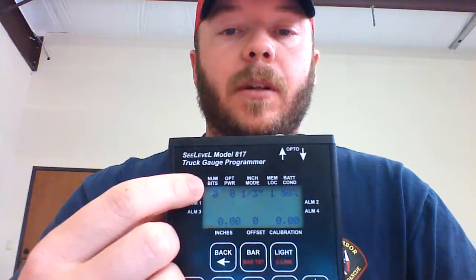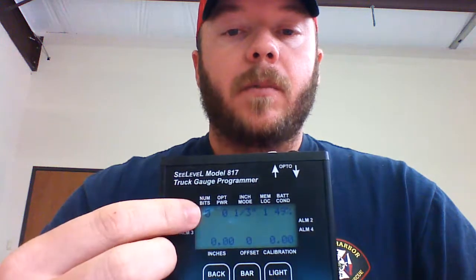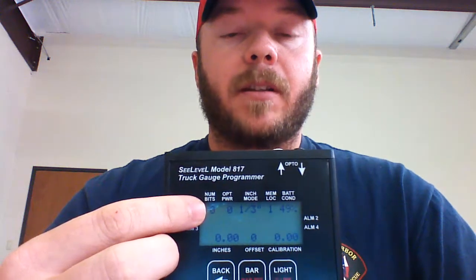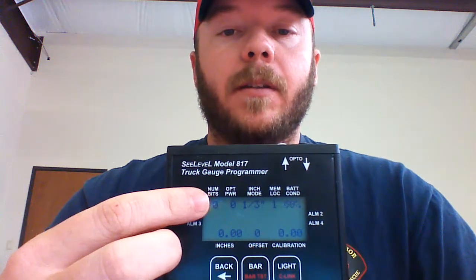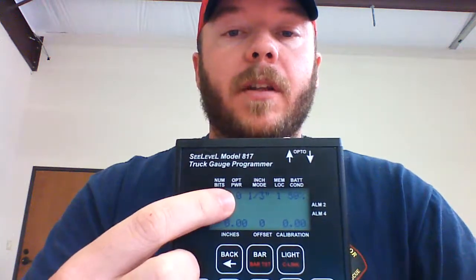And then when we get down to the little LCD screen here, we'll see some different labels. We're going to start with the number of bits. When you have the fiber from a sender bar plugged into the black fitting up here at the top, a bit number will pop up. Most of the time, 99% of the time, that bit number is going to be 8 bits. The bits are the amount of information that is transmitted. Another number that's going to pop up is your optic power. That is the signal strength coming through the fiber optic cable itself, being transmitted by the bar. So these two numbers will show up when a fiber from the bar is plugged into the black fitting there.